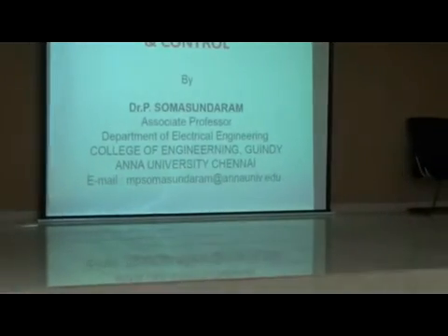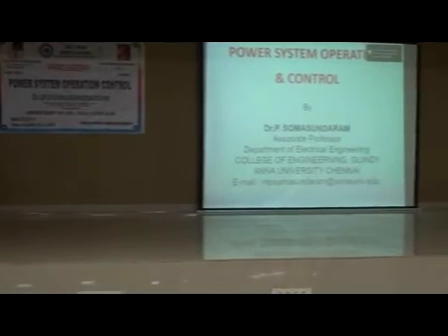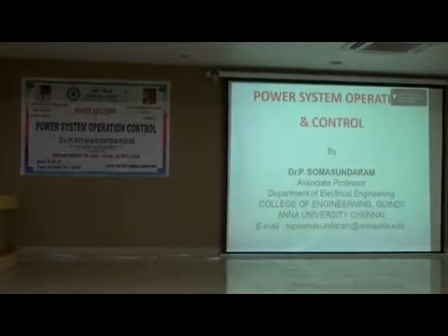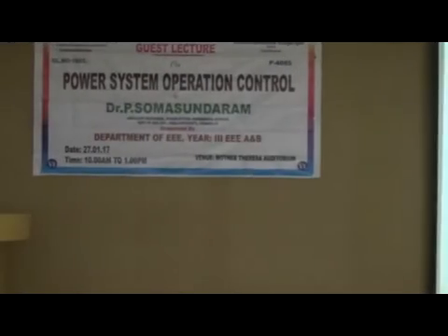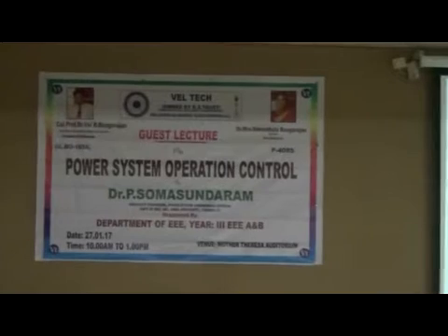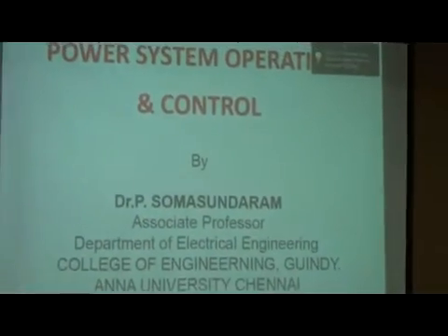But as the whole campus has a number of loads, for each load you have to assess the requirement of power from midnight to midnight, plot the load curve, and club them together. With that you will get the load curve for this entire campus. Like that, the operator also, if you are in the electricity board, has to do the same thing. And after getting the load curve, what is your requirement? Because you have to establish the grid.